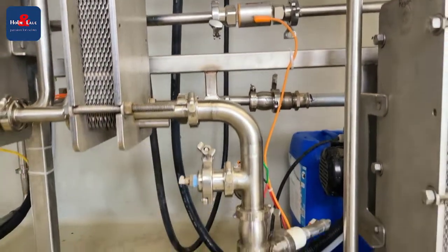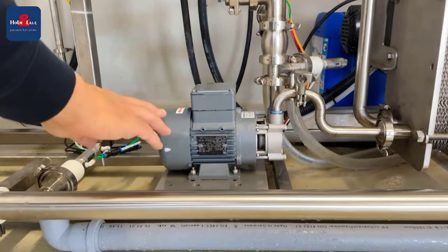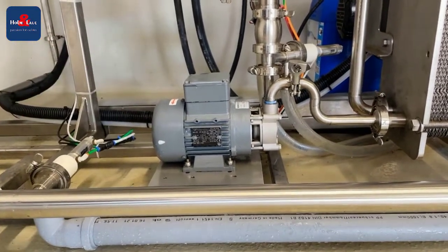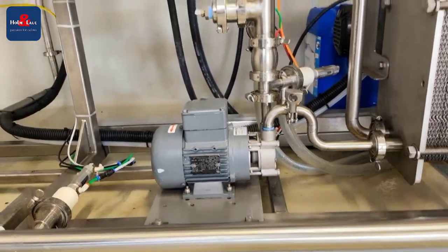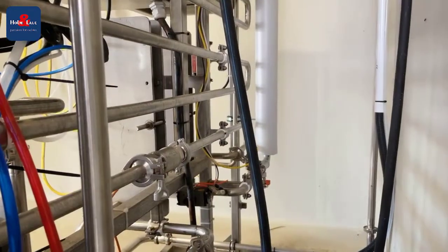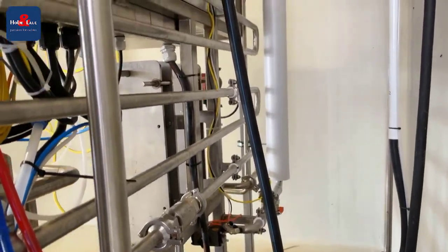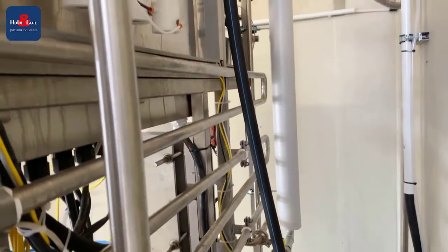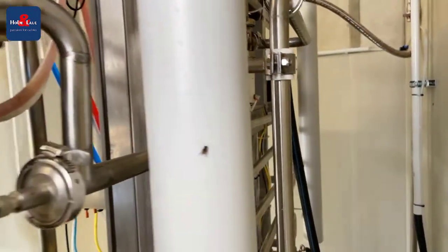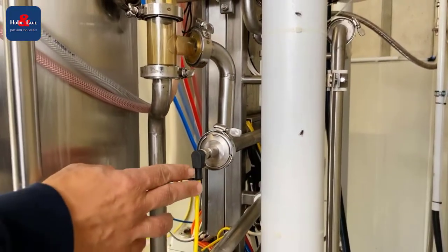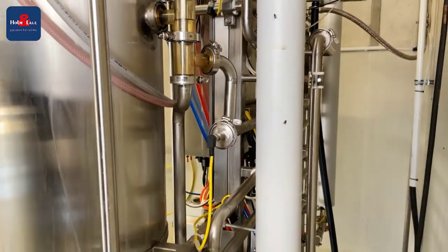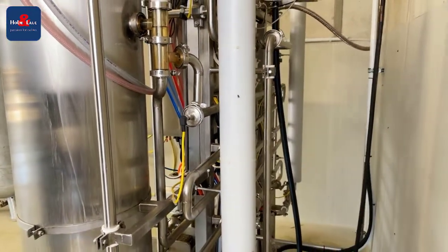This frequency controlled pump is managed by the control unit of the pasteurizer to keep exact time and temperature. At the end of the timing loop, another sensor measures the temperature and determines whether the required 73 degrees is still correct. Only then has the pasteurization been successfully completed.